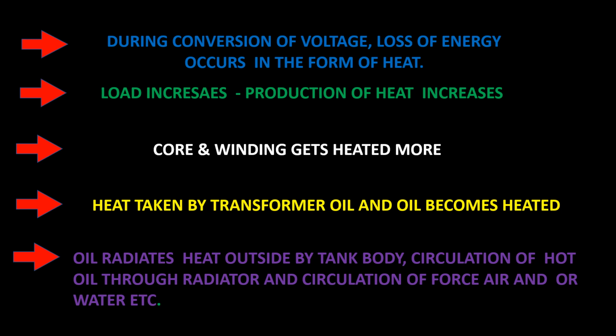When the temperature of the oil increases beyond its permissible limit, cooling systems or apparatus such as cooling fans, ONAF, cooling pumps, OFAF, even watering and radiator banks start acting to reduce the temperature to a suitable operating value for protection of the said transformer. When by any chance the main power supply fails, the standby power supply starts to act automatically.